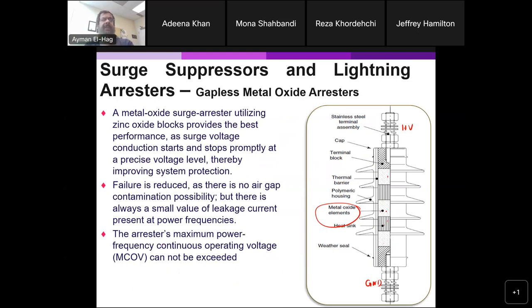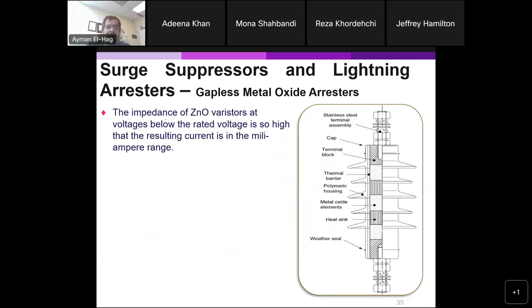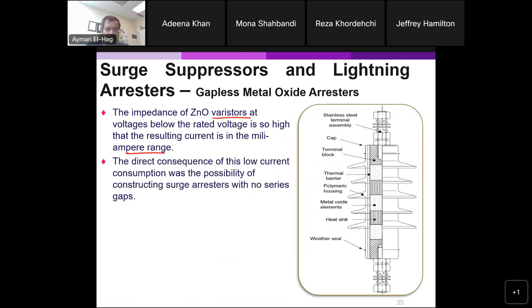An important parameter is the maximum power frequency continuous operating voltage — a certain voltage at which arrestors are designed to work continuously. The impedance of the zinc oxide blocks is extremely high, so the current is in the milliamp range — very small steady-state losses. Because of this high nonlinearity and extremely small current, there is no need to introduce air gaps between the blocks.